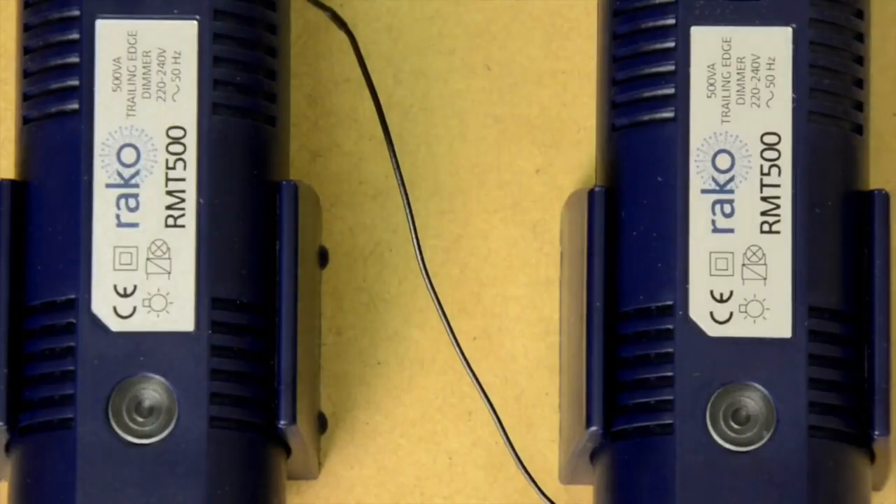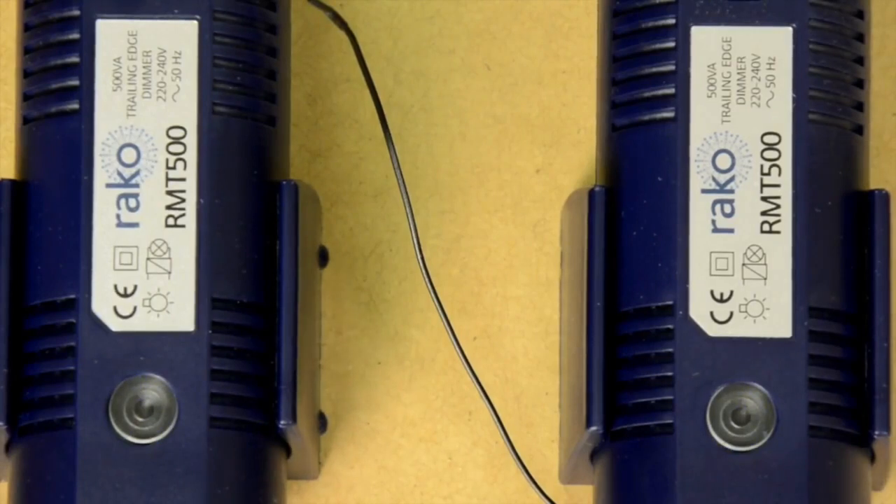Before we do so — which is covered in the video on manually programming a scene — it's worth checking that we've got everything right so far. The LED inside the dimmer module flickers every time it sees a message from a Rako device. It doesn't matter if it's programmed to respond to that device — it just flickers. So if you have a dimmer which flickers but doesn't do anything, it's probably not being addressed correctly.